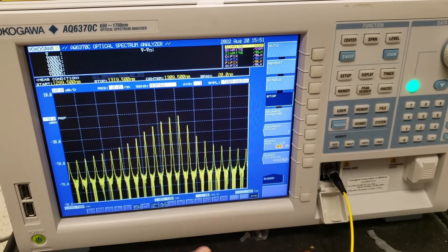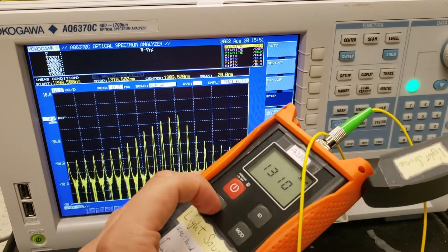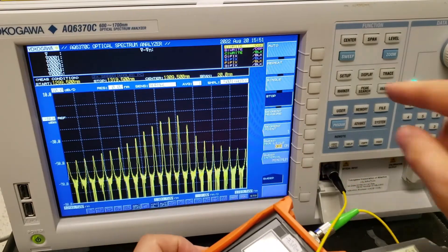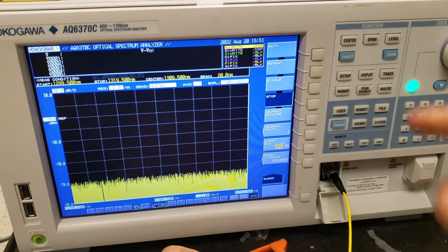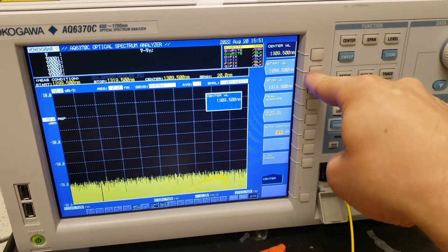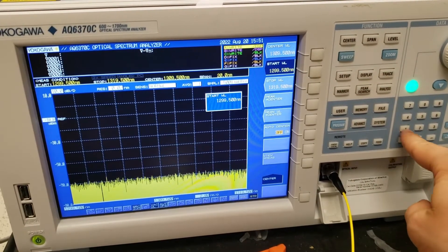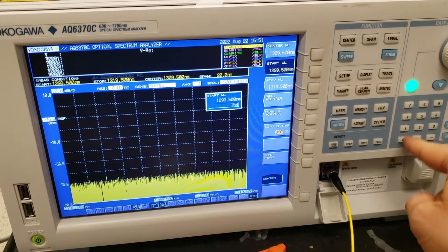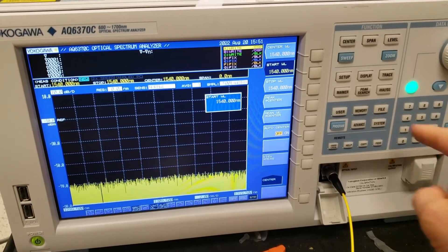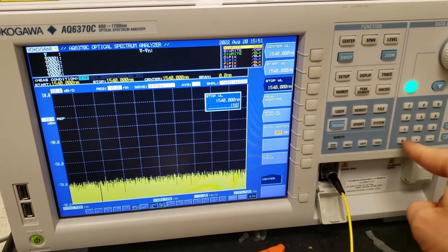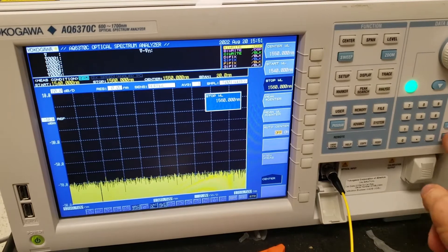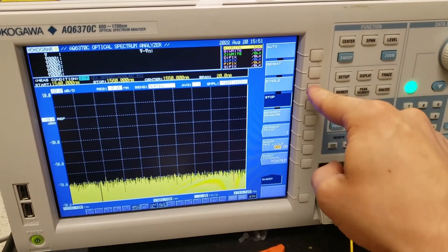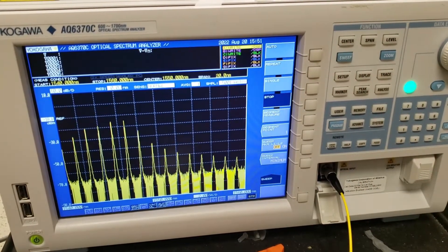So you can of course also switch this particular laser to other wavelengths, so let's maybe try that. I'm gonna switch to 1550, and if I sweep now we can see that this light here around 1310 has disappeared. So now let's adjust the center wavelength here. Let's go to 1540 perhaps, and stop wavelength and set that to 1560.